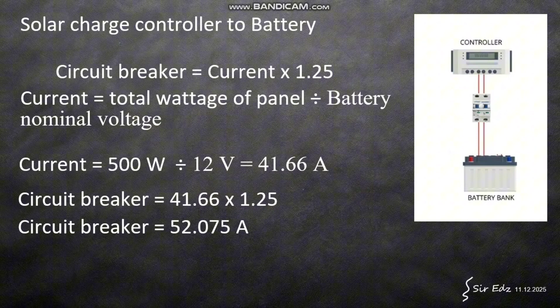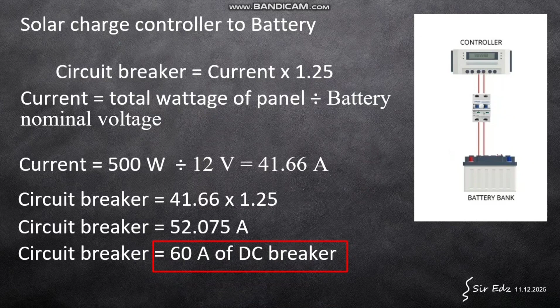Then we substitute the current into the circuit breaker formula, multiply by the safety factor, and we get around 52.075 ampere. Since there's no 52 ampere available in the market, we use the 60 ampere DC breaker.